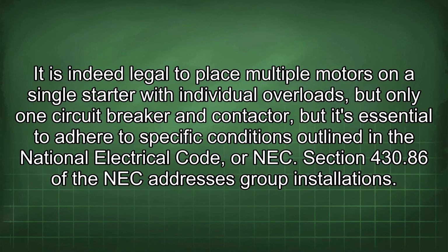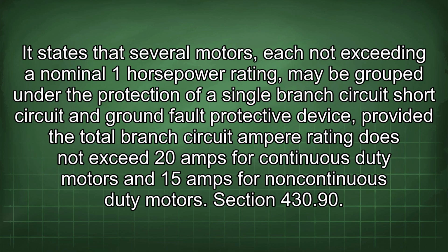It is indeed legal to place multiple motors on a single starter with individual overloads, but only one circuit breaker and contactor, but it's essential to adhere to specific conditions outlined in the National Electrical Code, or NEC. Section 430.86 of the NEC addresses group installations. It states that several motors, each not exceeding a nominal 1 horsepower rating, may be grouped under the protection of a single branch circuit short circuit and ground fault protective device, provided the total branch circuit ampere rating does not exceed 20 amps for continuous duty motors and 15 amps for non-continuous duty motors.